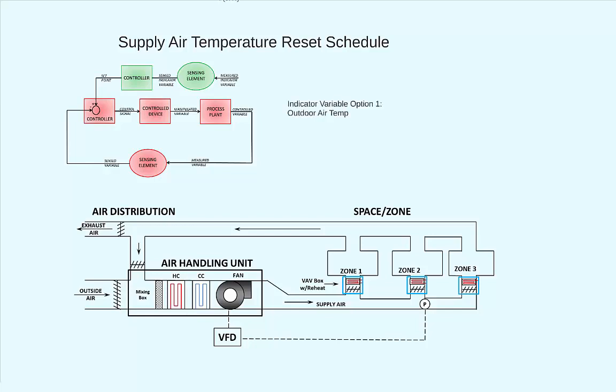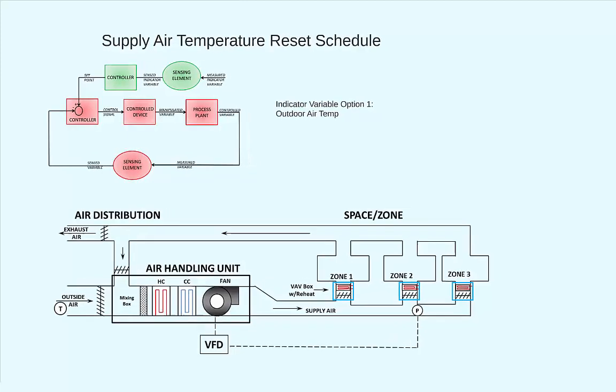First, we could change the set point based off of the outdoor air temperature. Here, we are basically assuming that when it is below a certain temperature outside, a large portion of the building is probably going to be in heating mode. Thus, we adjust the set point of the air leaving the air handling unit to minimize the waste of reheating such air. The temperature set point could follow a pattern like the one shown here.